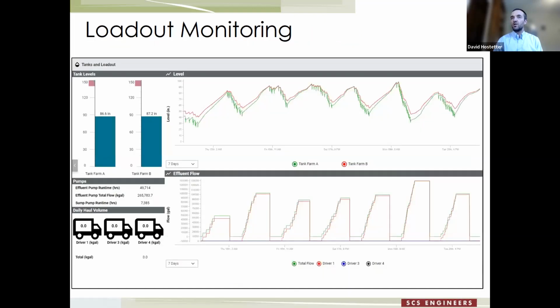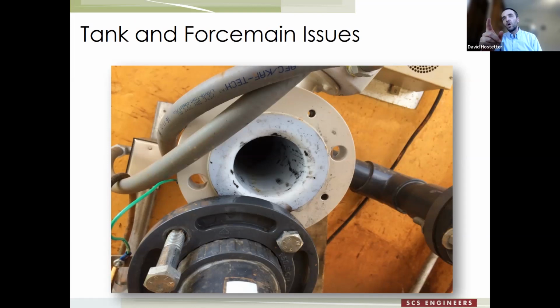Thanks. We had another instance, you can jump backwards, Diane, where we had literally just installed an RMC system. It was, I think, operational for 15 minutes, and we were looking at very similar to this, the amount of flow that was leaving the pump station. And we were also looking at the pump statuses, and we were looking at the level in the pump station. So through the RMC system, literally within 15 minutes of doing this, our now senior project manager, Sam Rice, was standing out there and was looking at the interface and was seeing that both of the pumps were running, but the level was going up in the pump station.